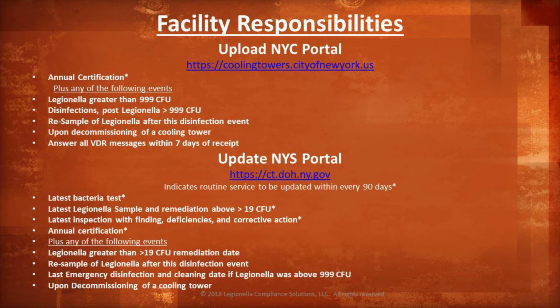The following information must be uploaded to the New York State portal: the latest bacteria test every 90 days, the latest Legionella sample, any Legionella remediation above 19 CFU, the latest inspection of findings including deficiencies and corrective actions, and your annual certification. Furthermore, you must upload the corresponding documents if any of these events occur. Legionella is greater than 19 CFU. Legionella results greater than 19 CFU post-disinfection, resampling of Legionella after disinfection, and decommissioning of a cooling tower.